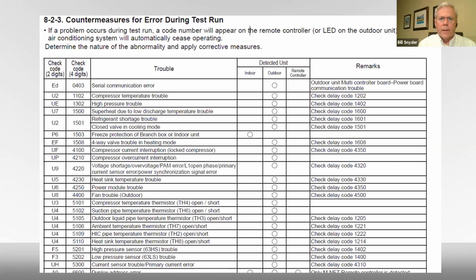Looks like a thermostat, what we call a controller. On the controller, it may be flashing U4, U4. Okay, U4, if you look over here, there are five different things that could be U4. They're all thermistors: pipe thermistors, outdoor thermistors, ambient thermistors, just different thermistors.